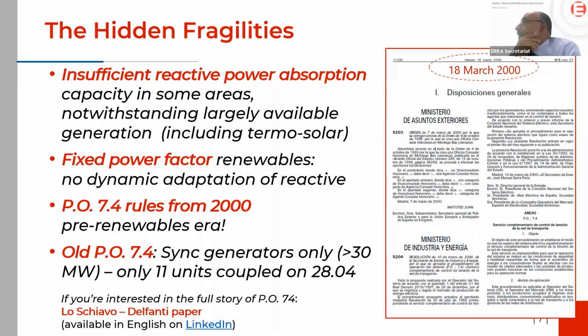But these thermosolar units are not allowed to contribute to voltage control because of the old procedure, although they are absolutely adequate for that. There are other issues too, like fixed power factor for renewables. So there is no role for renewables to contribute to voltage control - all the rules for voltage control are very inadequate.